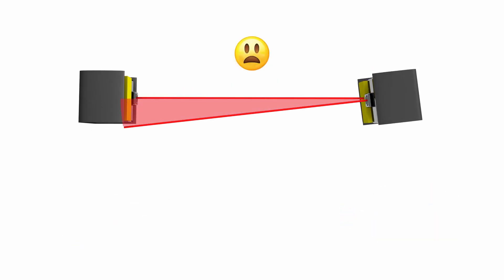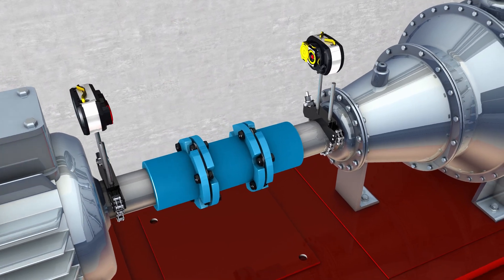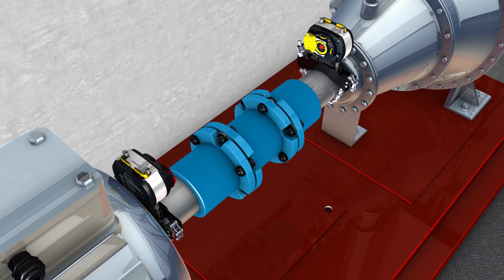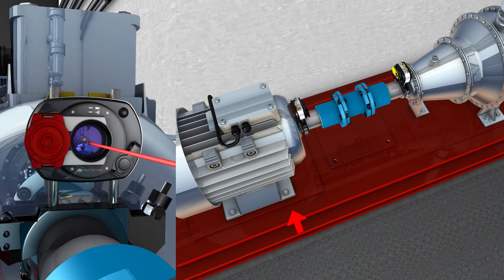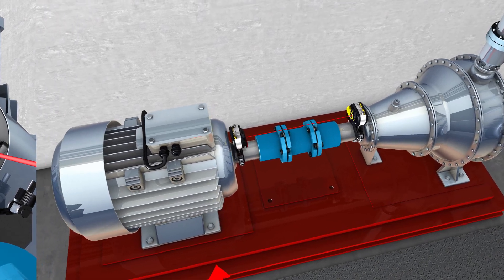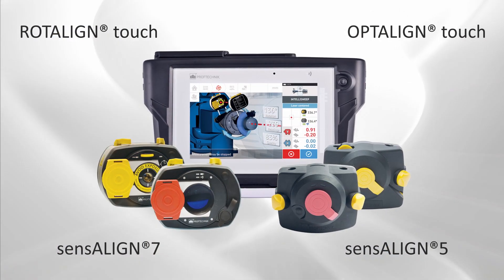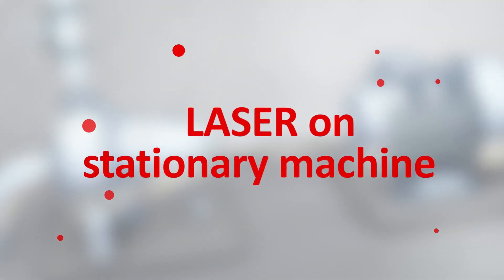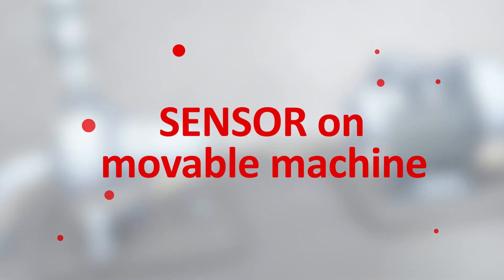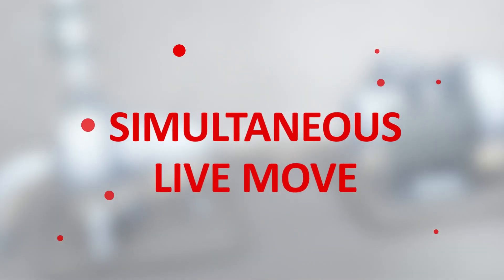In a nutshell, here is what to do: always place the laser on the stationary machine — here, the pump — and the sensor onto the movable machine — here, the motor. When you move the motor, the laser beam stays within the detector range. This is what makes using the sensALIGN single laser technology superior. Using OPTALIGN touch or ROTALIGN touch, always mount the laser onto the stationary machine and the sensor onto the movable machine.